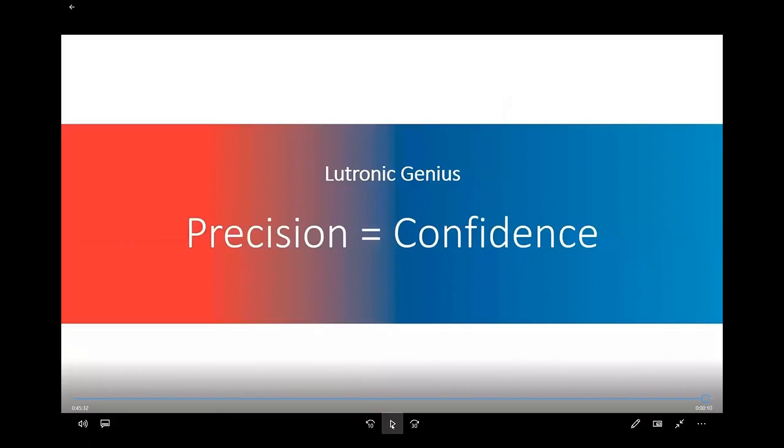So just kind of going back to the settings question. A lot of people are wondering about using the millijoules per pin, is that easier, do you think, or for those that are used to using manual settings, should they continue to use those? Well, I think if you feel comfortable, the millijoules per pin is a good way to go. If you start using that a lot, you'll become comfortable with that. Again, just multiply. Like say you were doing 30 millijoules per pin. If you do that, there's certainly nothing wrong with that, and you'll end up delivering about 1.5 joules. You can do it that way, or you can do 5 watts times 150 milliseconds. So it really depends on what you're comfortable with.